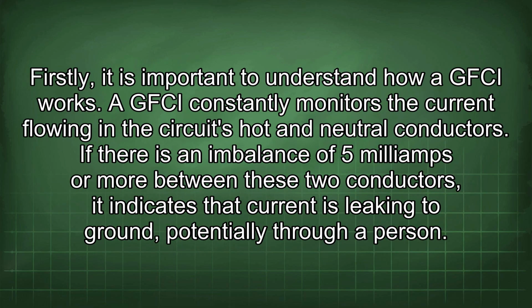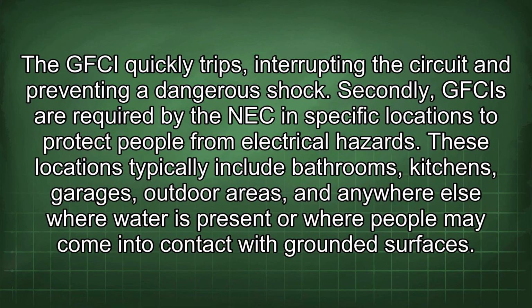Firstly, it is important to understand how a GFCI works. A GFCI constantly monitors the current flowing in the circuit's hot and neutral conductors. If there is an imbalance of 5 mA or more between these two conductors, it indicates that current is leaking to ground, potentially through a person. The GFCI quickly trips, interrupting the circuit and preventing a dangerous shock.